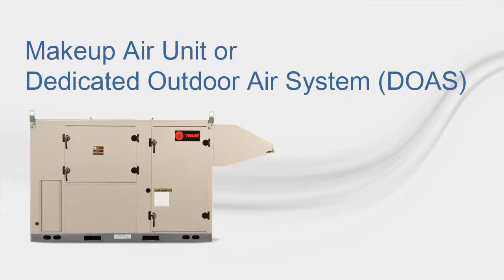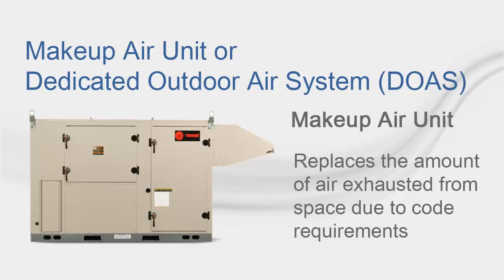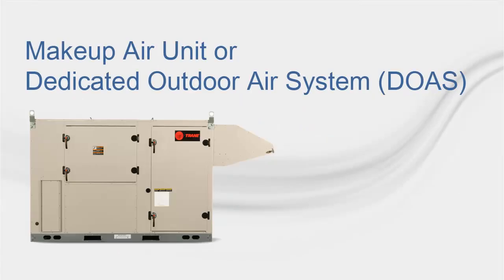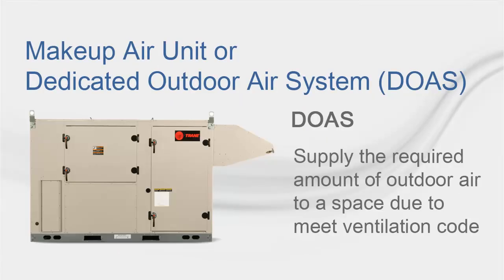A makeup air unit is sometimes also called a dedicated outdoor air unit. Sometimes they may be the same thing, but it can be important to distinguish between these terms. The primary function of a makeup air system is to replace the amount of air being exhausted from a space due to code requirements. The primary function of a dedicated outdoor air system is to supply the required amount of outdoor air to a space to meet the ventilation code.